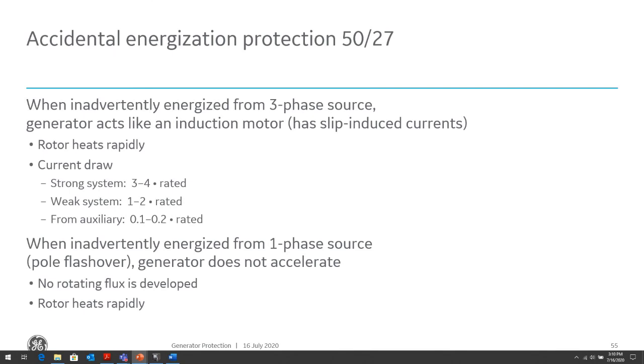There are two types of energization: inadvertent energization, three-phase and single-phase. In the case of the pole flashover or breaker flashover, it's usually a single pole flashing over, so it'll be a single phase condition. What happens during this condition is that the induced currents within the rotor start to heat up rapidly. Depending on the system that it's connected to, you can have a very high draw, up to 3 to 4 times the rated current of the machine, which will cause damage to the machine if not detected.